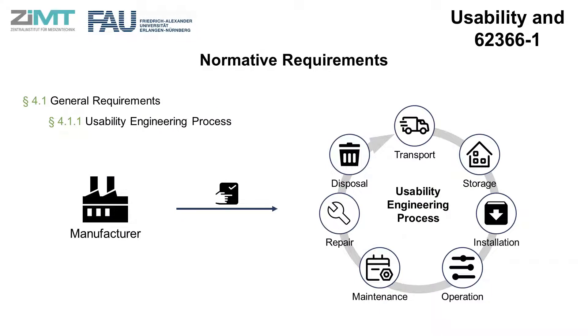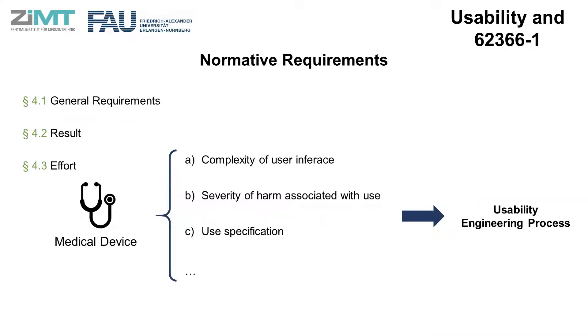As written in the general requirements of this standard, the manufacturer shall establish, document and maintain a usability engineering process to provide safety for the patient. This process shall address user interaction with the medical device according to the accompanying documentation, including but not limited to transport, storage, installation, operation, maintenance, repair and disposal of the device. The level of effort and the choice of methods and tools used to perform the usability engineering process depend very much on the device and may vary based on the severity of harm associated with the use, the use specification, and the size and complexity of the user interface.